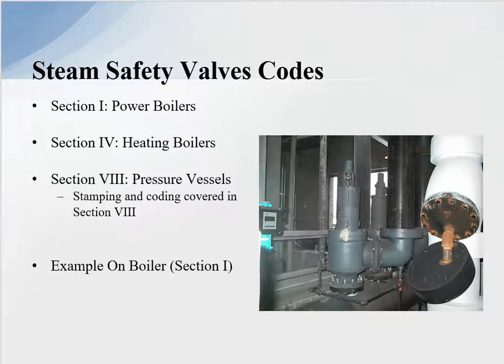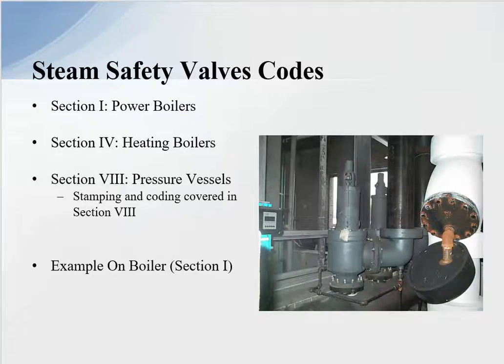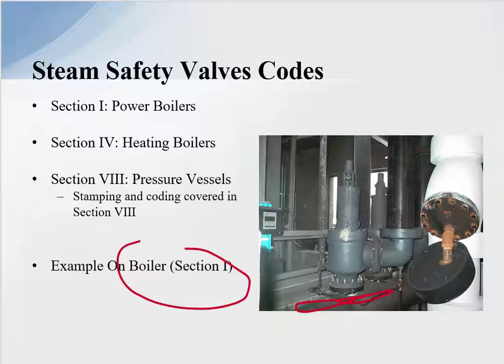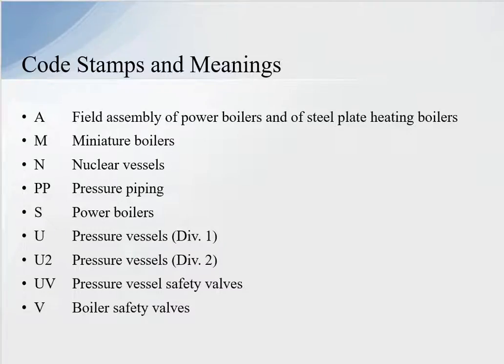In a steam system, we look at Section 1 for boilers or power boilers, Section 4 for heating boilers, and Section 8 for pressure vessels away from the boiler in the steam system. Anything away from the boiler we are typically looking at Section 8 safety valves. An example shows a safety valve located on a boiler, which would be Section 1. The code stamps are: A, M, N, PP, S, U, U2, UV, and V. For example, PP is pressure piping, S is for power boilers, U is for pressure vessels, and V is for boiler safety valves.